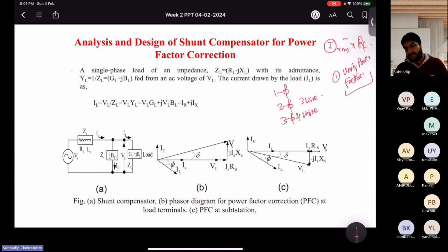Even if you are attaching many non-linear loads or distorted loads, they want from their end, if they are sitting at the substation or distribution systems, then if this is the point from where they are injecting the power at this bus, what they want is, if the bus voltage is V, they want their current I to be as much in line as possible to the voltage. So this will enable them to throw more power at the point of common coupling, incurring minimum amount of line losses. Because if it was not unity power factor, then the line losses will be more. But they do some arrangements at their end to correct their power factor.